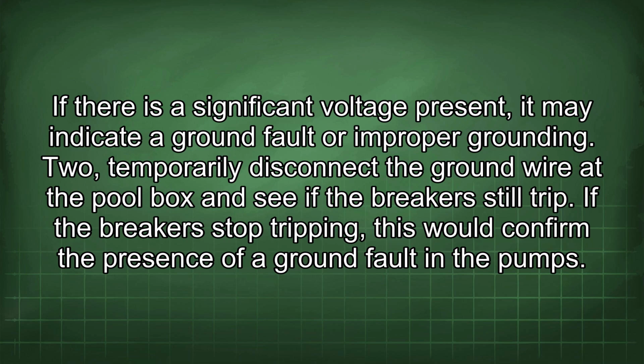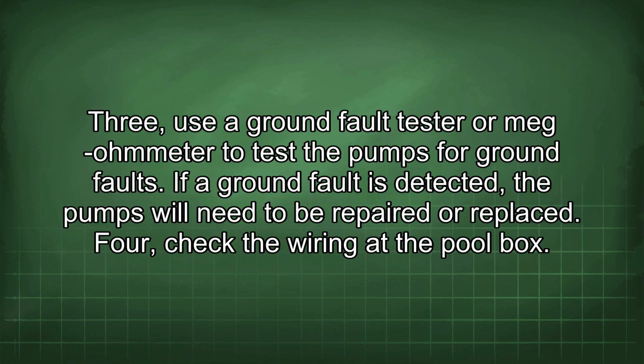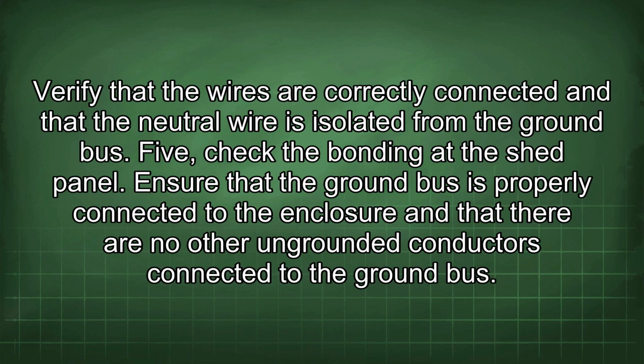2. Temporarily disconnect the ground wire at the pull box and see if the breakers still trip. If the breakers stop tripping, this would confirm the presence of a ground fault in the pumps. 3. Use a ground fault tester or megohmmeter to test the pumps for ground faults. If a ground fault is detected, the pumps will need to be repaired or replaced. 4. Check the wiring at the pull box. Verify that the wires are correctly connected and that the neutral wire is isolated from the ground bus.